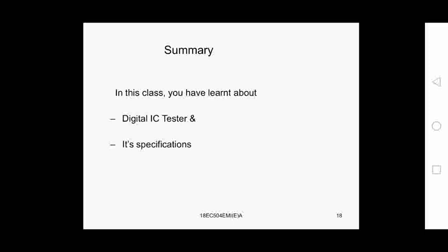And you will have the initialization switch, which is for presetting verification. That is, without placing any IC for test, you can check the presetting verification by pressing the initialization test key. And you will have the test pattern generator.